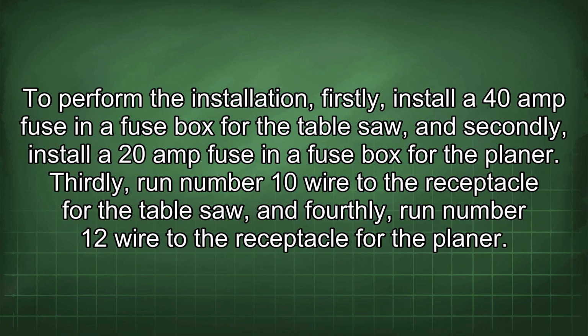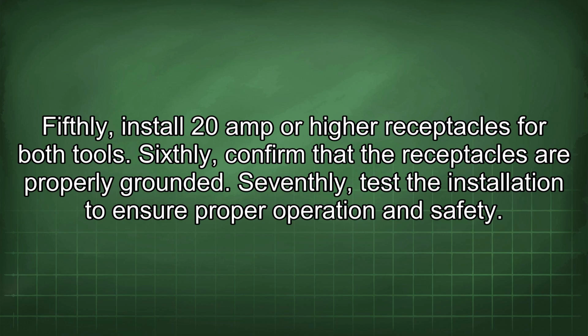To perform the installation, firstly, install a 40 amp fuse in a fuse box for the table saw, and secondly, install a 20 amp fuse in a fuse box for the planer. Thirdly, run number 10 wire to the receptacle for the table saw, and fourthly, run number 12 wire to the receptacle for the planer. Fifthly, install 20 amp or higher receptacles for both tools.